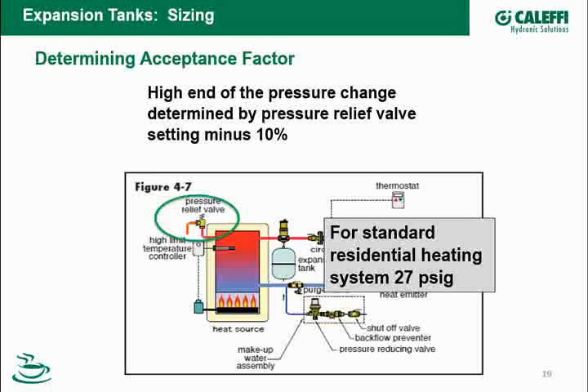So for a standard residential heating system, the expectation is I'll probably push the pressure up, possibly up to 27 psi, to give me good expansion range, but I want to stay below 27 to make sure the relief valve doesn't lift. So now I have the information for my pressure side. Minimum pressure is going to be 12 psi. Maximum pressure is going to be 27.